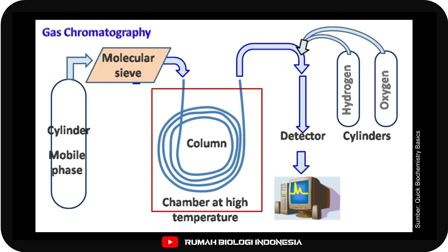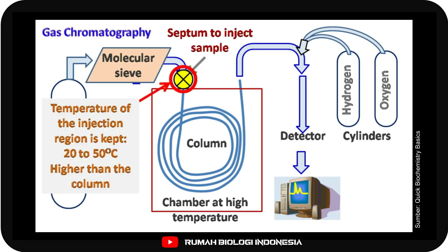Just before the column, there is a septum that allows injection of the sample. The temperature of the injection region is kept 20 to 50 degrees Celsius high as compared to the column. This allows rapid volatilization of the sample.